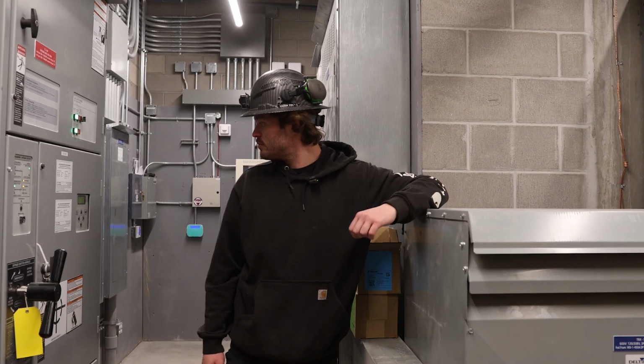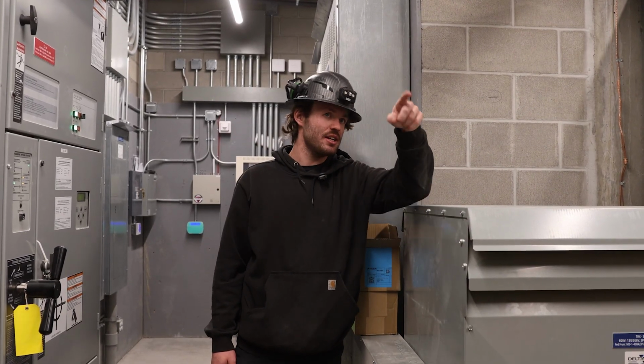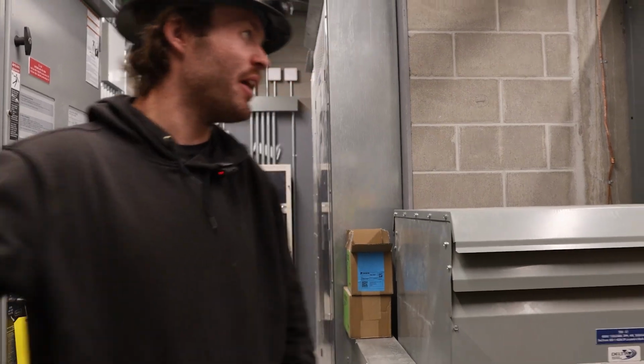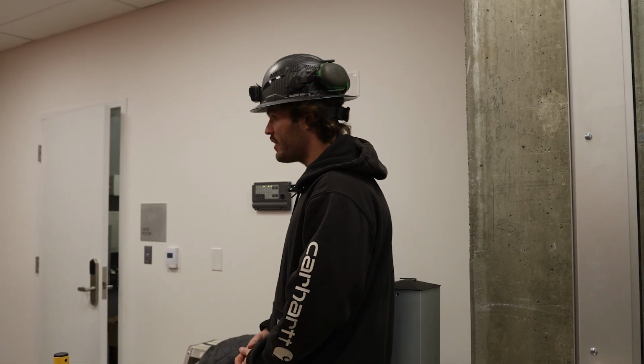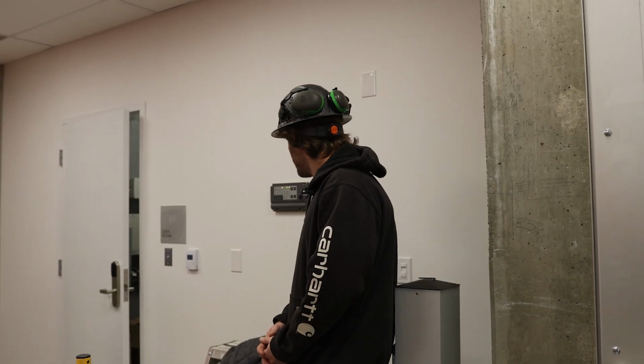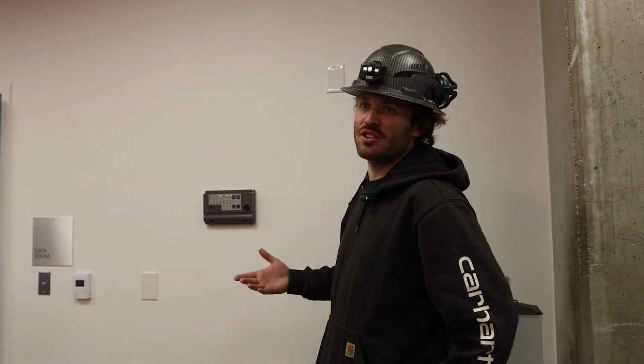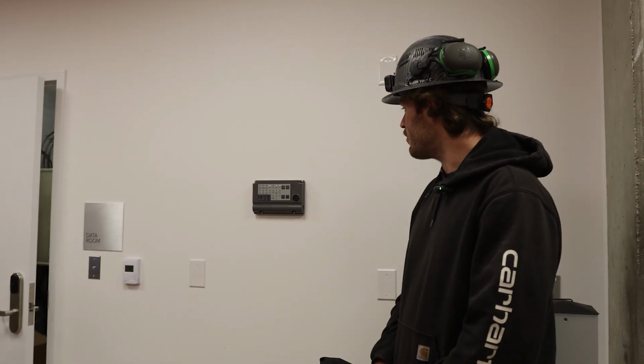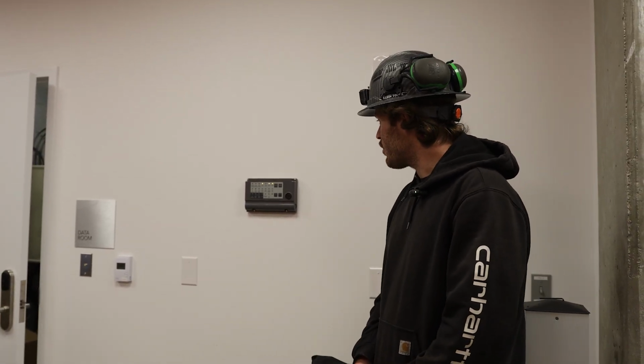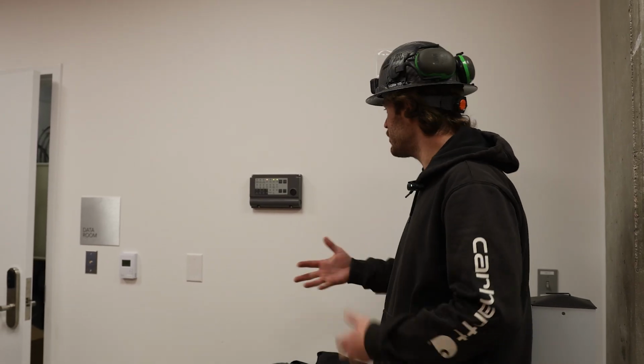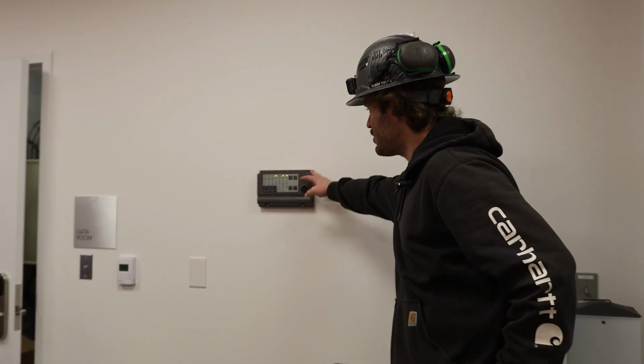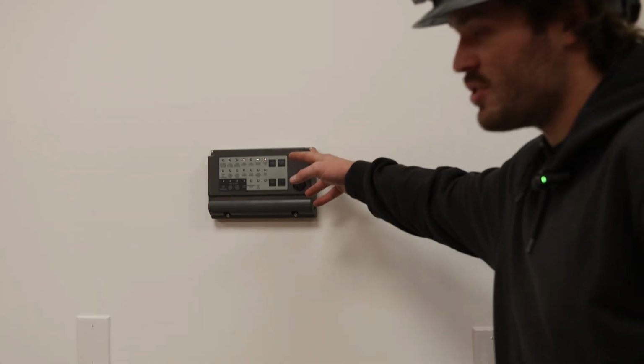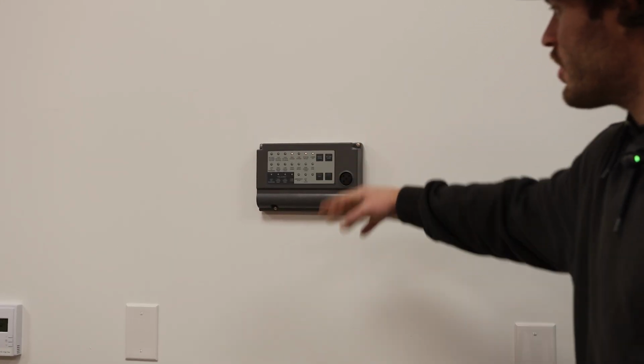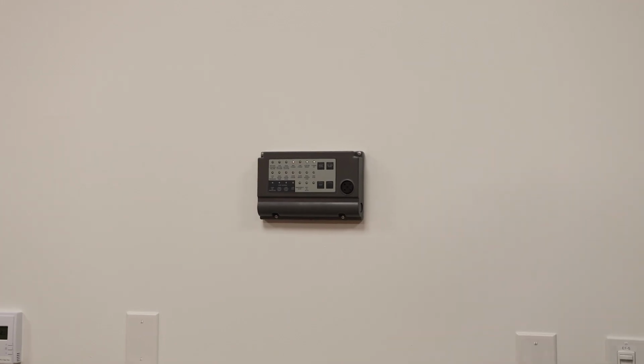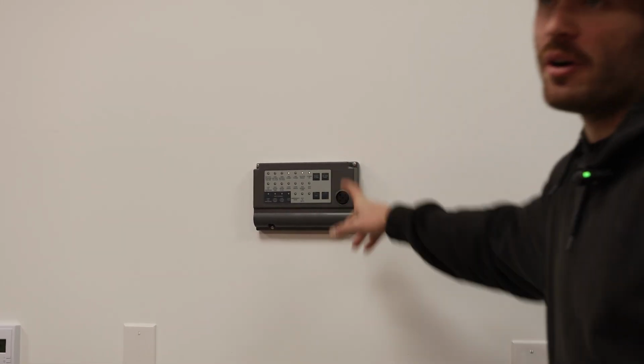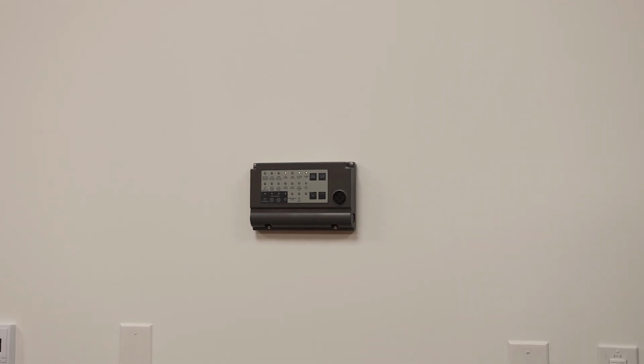One more thing to show you guys inside the main building, the annunciator panel. In the office is the remote annunciator panel for the generator. This is connected just to the generator itself. It is a panel which relays messages from the generator and shows it in the form of a light or a buzzer alarm. If the generator were to throw a fault, it's going to illuminate a corresponding light for said fault, or there are generic ones. If the generator is running, it's going to light up generator run. If it were to have a communication error with the generator, it's going to light up, and it's going to buzz extremely loud, where it'd be audible throughout easily the office and main floor here.